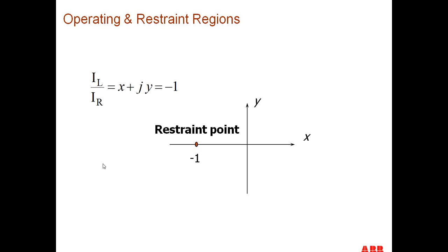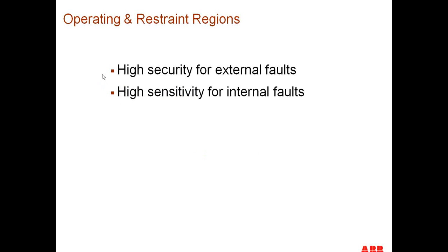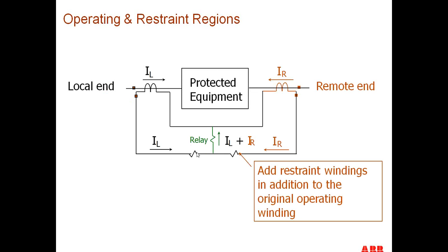But we know in real practice that IL and IR aren't quite equal to each other because of other factors. So in order to make the relay much more secure for external faults and sensitive for internal faults, we put a restraint quantity in the circuit, so that we not only have an operate quantity, but we also have a restraint quantity. Now we not only have to have an operate current, but we also have to have an operate current above a certain restraint current level in order for the relay to operate properly.